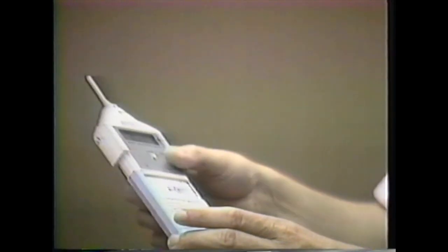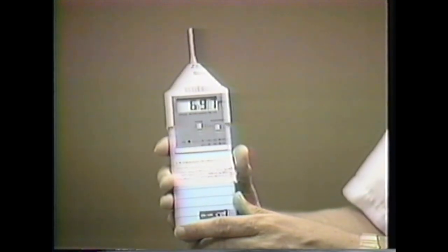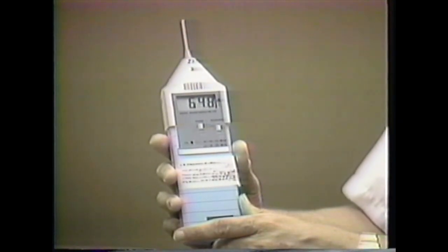As far as powering this unit, it's powered by 4 AAA batteries, which can be observed by pressing on the center plate. You'll have 2 in the front and 2 visible from the rear. It's extremely important that we use fresh batteries, and if we anticipate storing this for a prolonged period of time, that we remove the batteries to prevent damage that might occur because of leakage or prolonged storage effects.